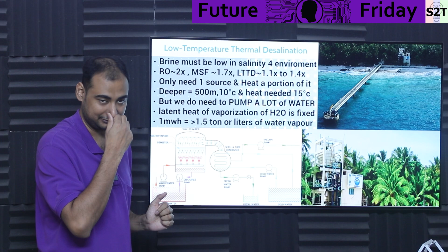Some designs can go very low. This one is 500 meters, 10 degrees Celsius. You only need to raise the temperature from 10 degrees to 15 degrees Celsius, not all the way to 100 degrees, because of the partial vacuum.